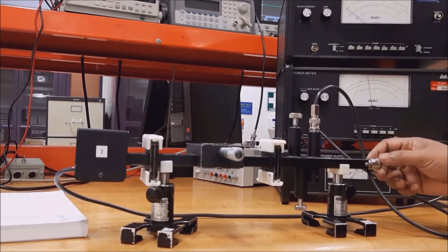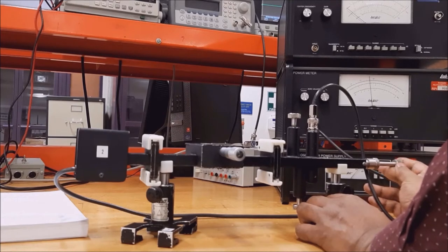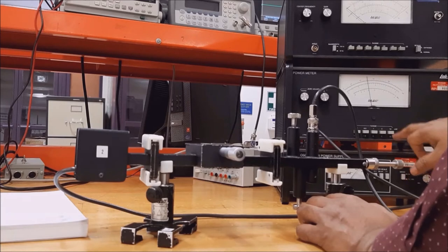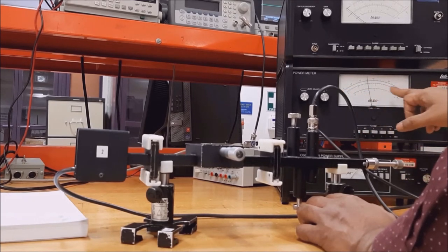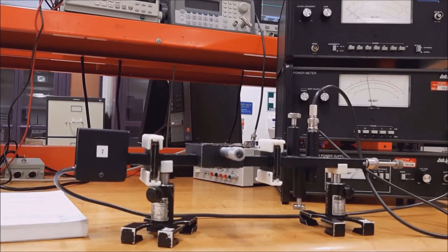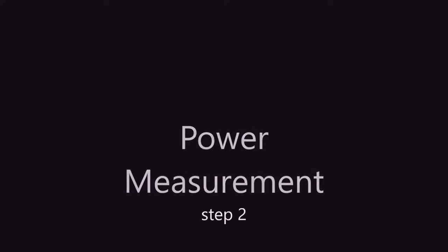So now we log this. We got the highest power and we log this position. So this is how we can find the maximum power reading for adjusting the thermistor to its maximum power level. So almost in every experiment we need to adjust the thermistor mount.